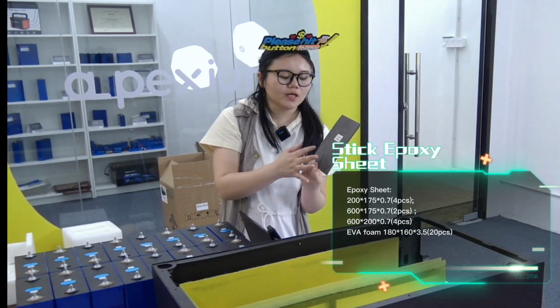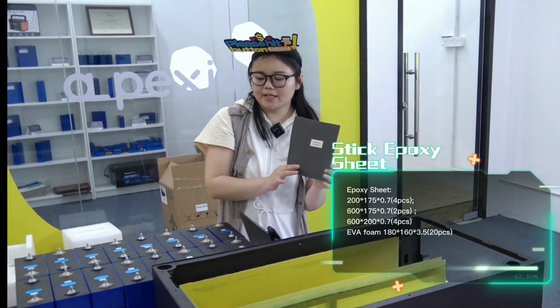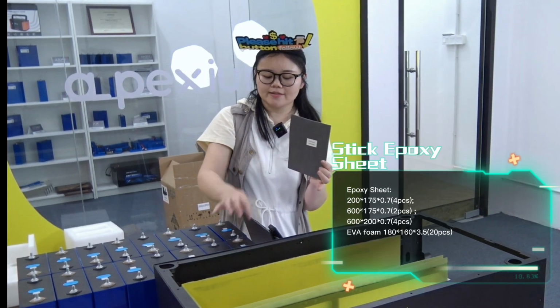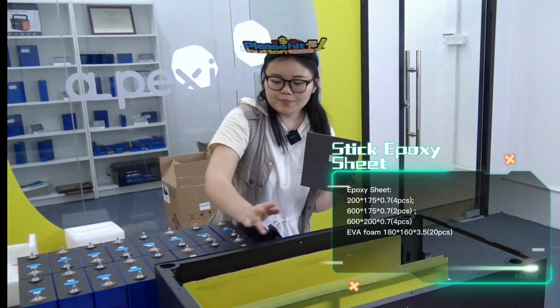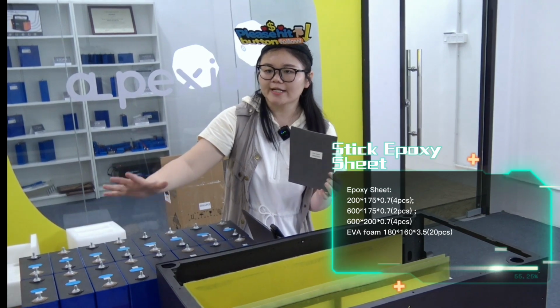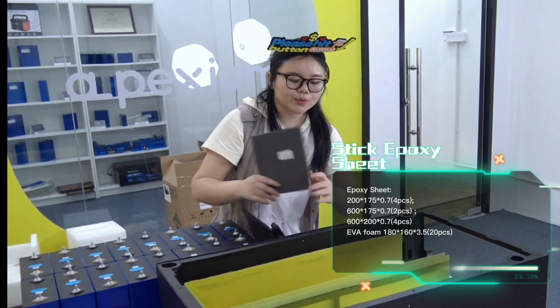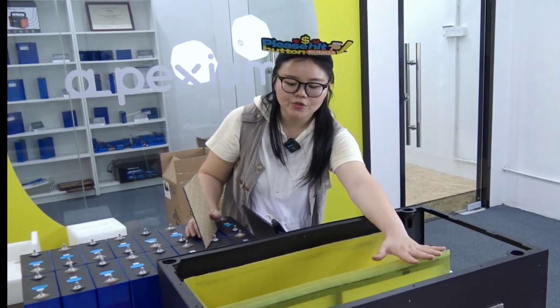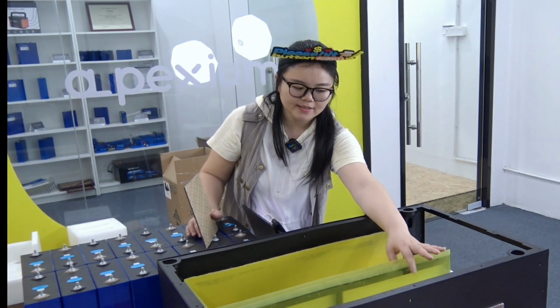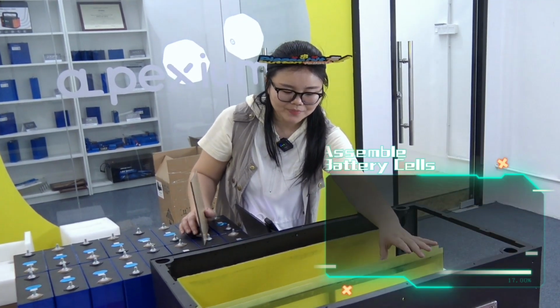This EVA foam, 20 pieces, is included in the packing list, and each one you need to stick on the battery one by one. Make sure the battery series direction conditions are correct and put into the battery case. Before putting in, we already stick the insulation separators inside the battery metal box.